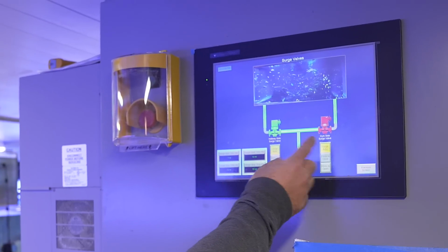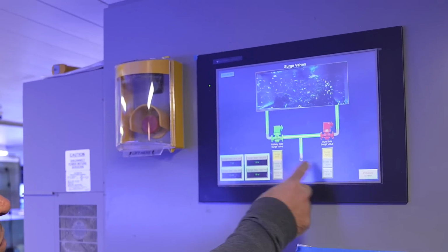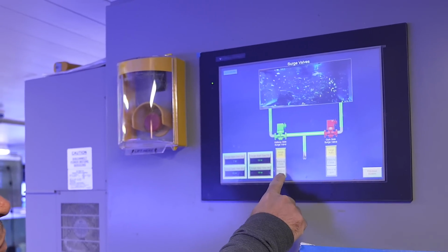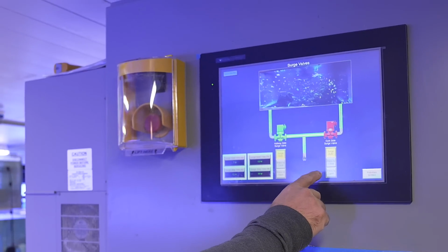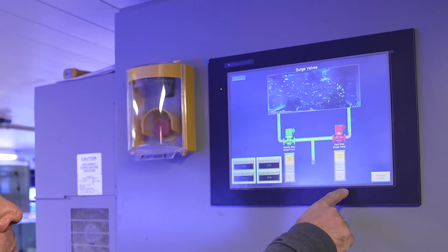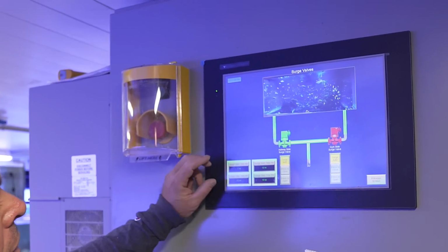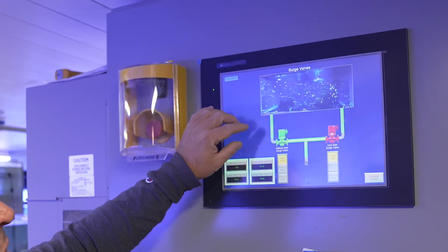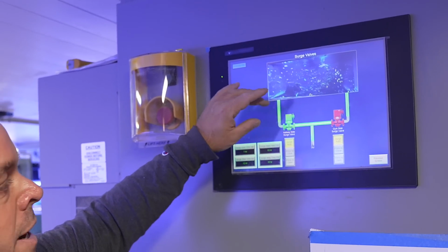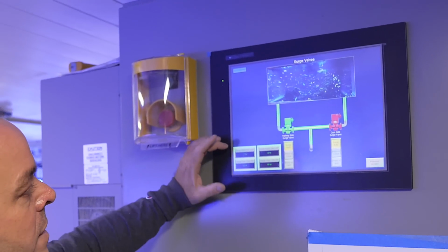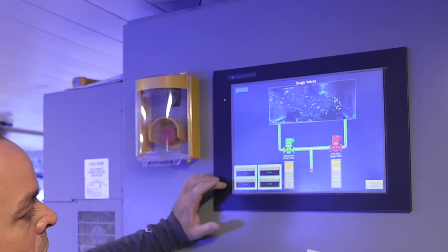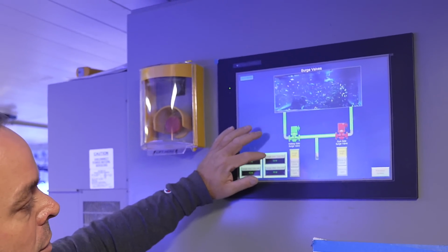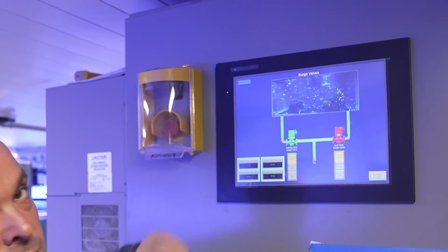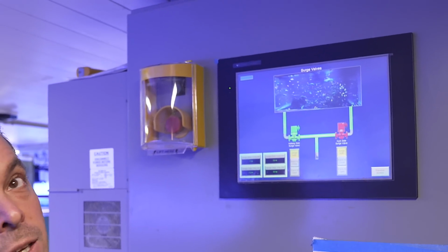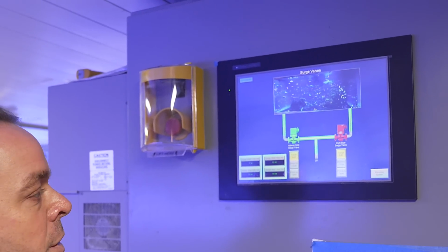Here we have the surge valves, one being open, one being closed. They're both in auto mode. We can also lock them to close where they won't do anything, and we can also lock them to open where they'll both be on. Like I said, they're running a subroutine that's random on and off times, and they start at 7 a.m. and run to noon. They take an hour break and they run from 1 o'clock to 6 p.m. and then they just automatically go to off so that there's a calming period in the tank.